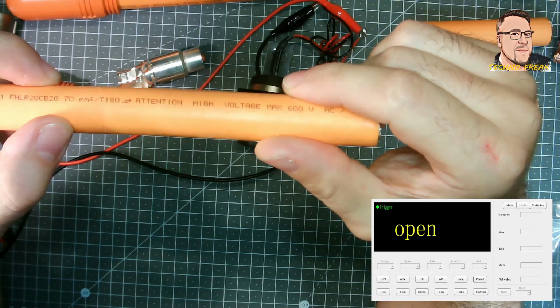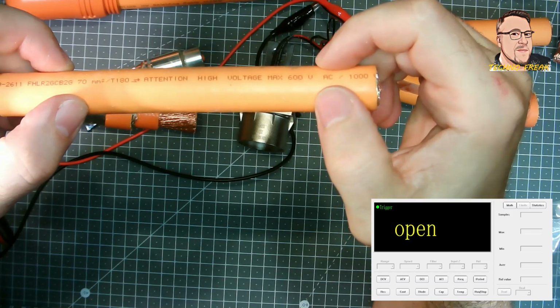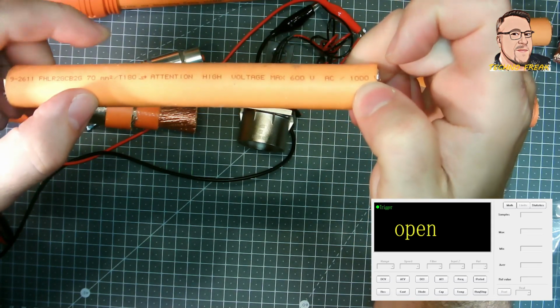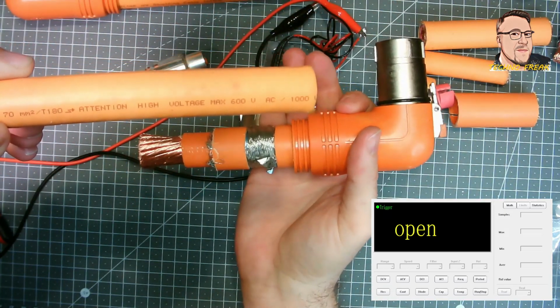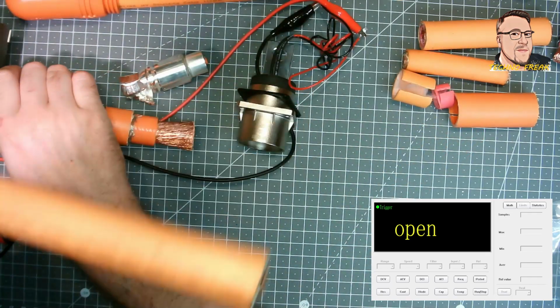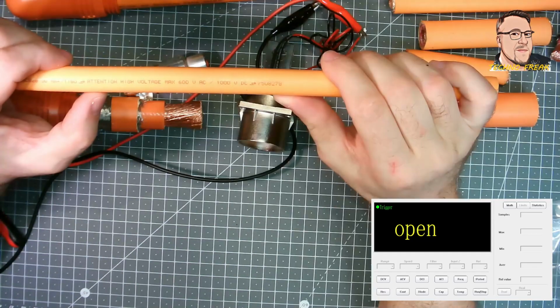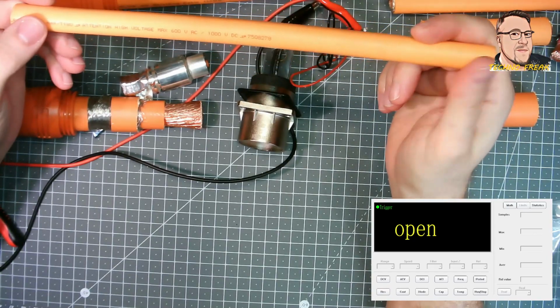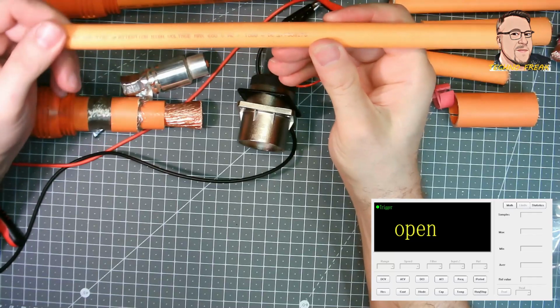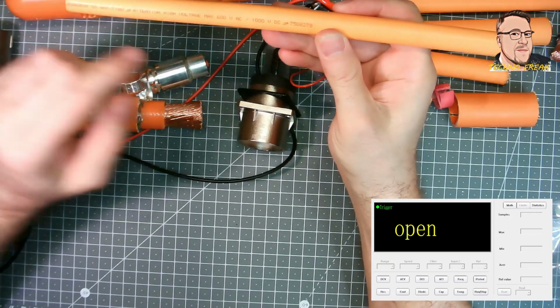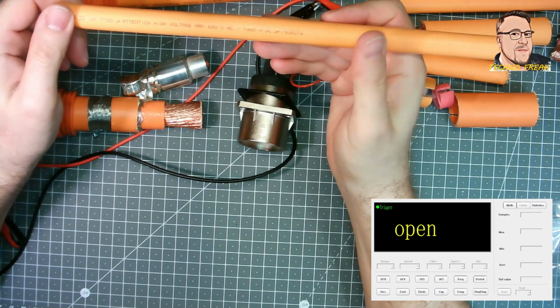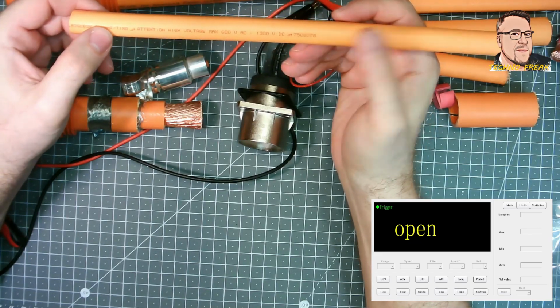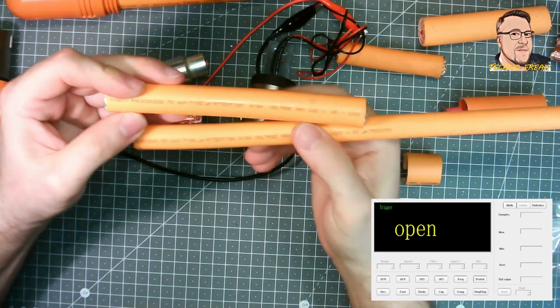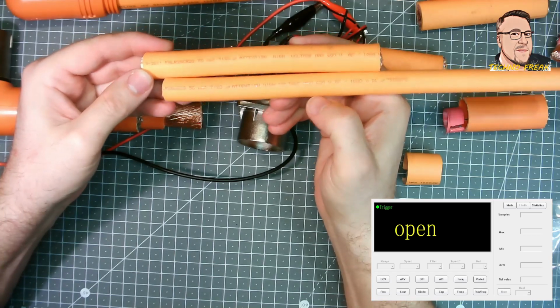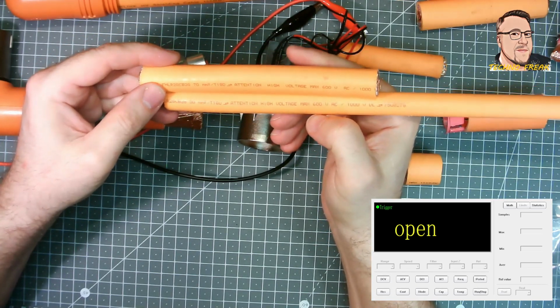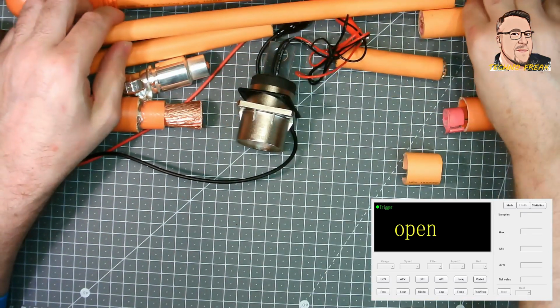70 mm square, and the maximum AC voltage is 600 and DC is 1000. This one is 1500, 1.5 kilovolts. This is the 1 kilovolt DC. Attention, high voltage. Any orange cables in all electric vehicles, you can find the orange cables, which will definitely be to that rating. 70 mm square. Oh, sorry, this one is 50 mm square. This one is 70. It's not a huge difference. The same voltage rating, and definitely different current rating depending on the size.